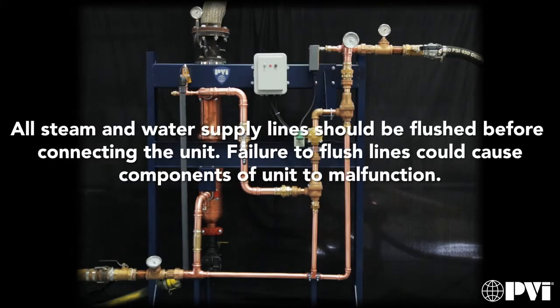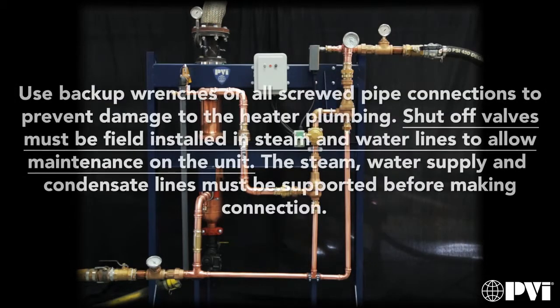All steam and water supply lines should be flushed before connecting the unit. Failure to flush lines could cause components of the unit to malfunction. Use backup wrenches on all screwed pipe connections to prevent damage to the water heater plumbing. Shut-off valve and unions are installed in steam and water lines to allow maintenance on the unit. The steam, water supply, and condensate lines must be supported before making connection.